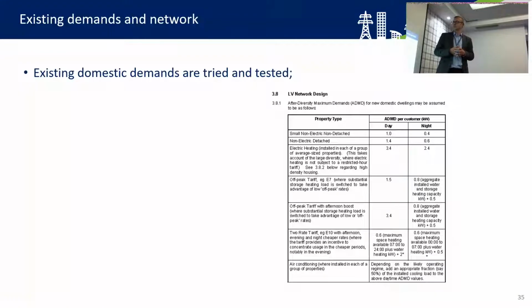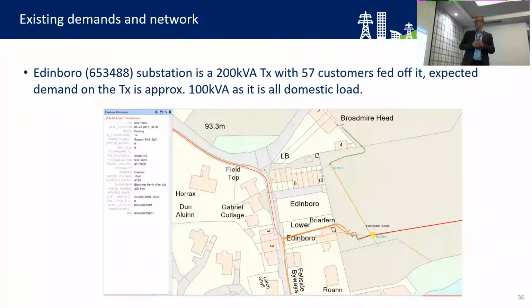So on the next slide, this is a bit of an example - one of our asset records. We've got an existing substation here with 200 kVA, 57 customers fed off it. So we'd expect to see no more than 100 kVA of domestic load on that, because these will all be gas heated, detached and non-detached properties.